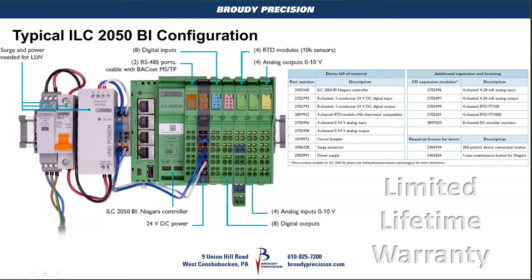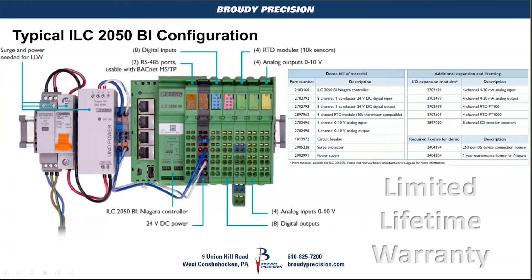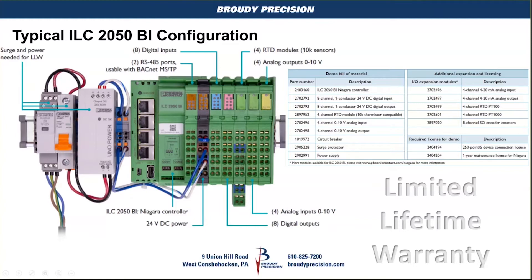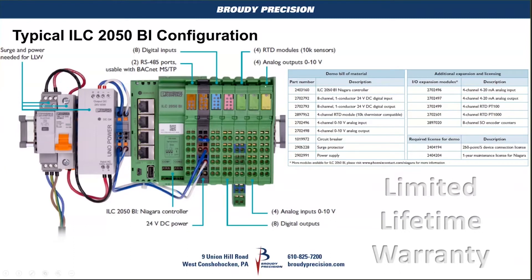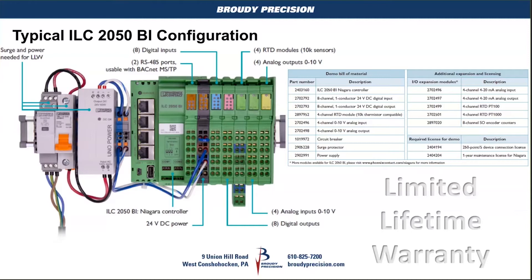If you look at what's here, you have the ILC 2050 BI from the black module to the left. And then from there, there's a digital input, digital output, a 10K thermistor, voltage input, analog inputs, and RTDs. You can see how you set this up. They just plug into the module to the left. There's a tab across the top. You can take the terminal part off the board, so if you had to replace any hardware, you wouldn't have to do any unwiring.